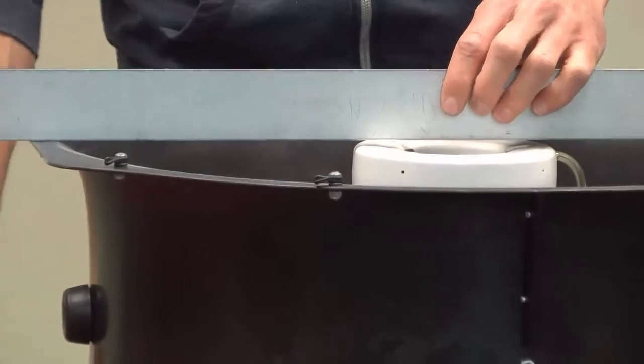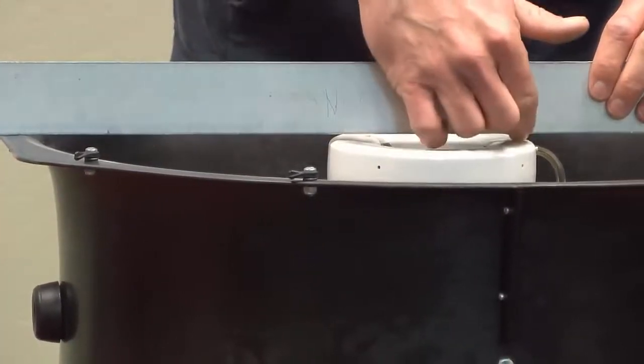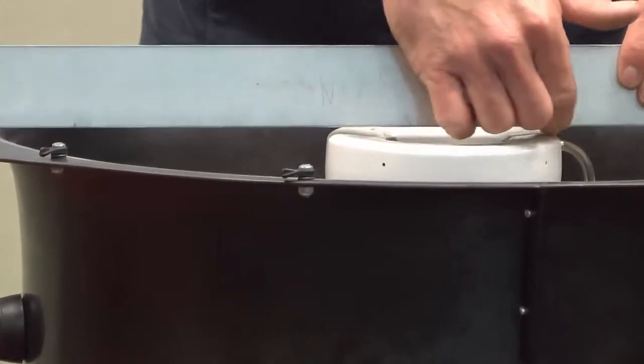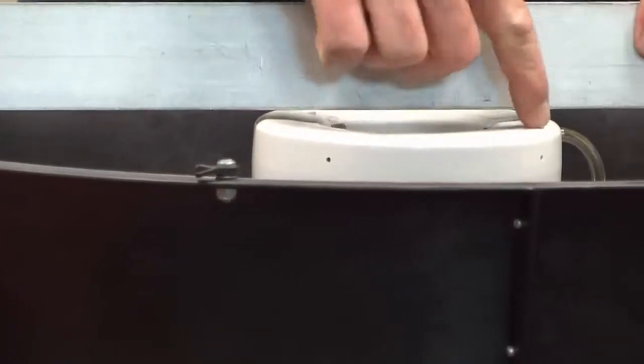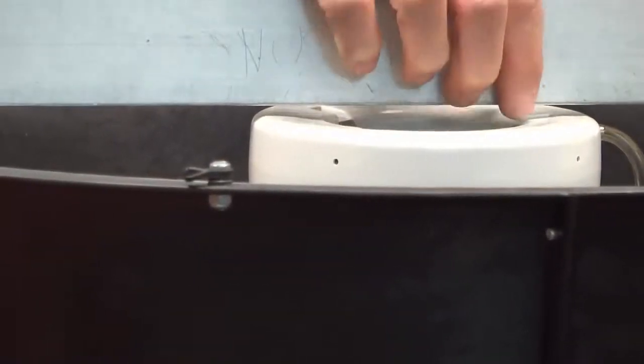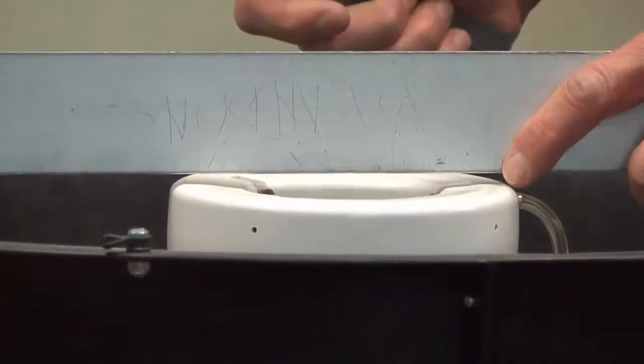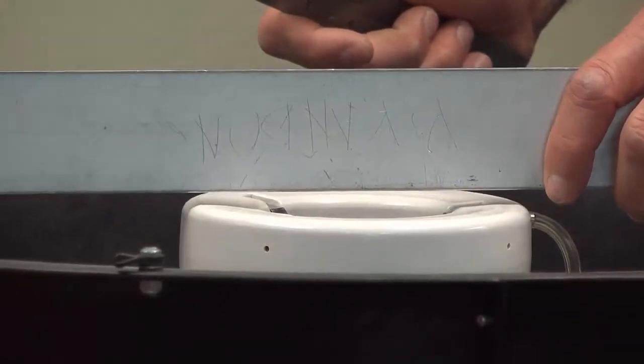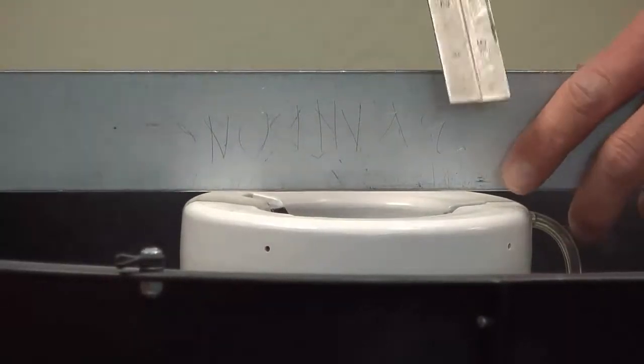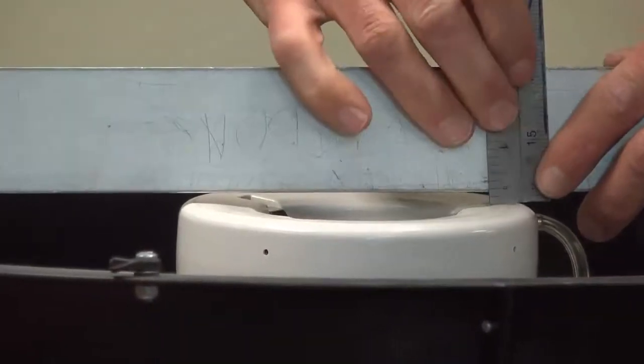Basically what we're going to be measuring is this gap between the bottom edge of our ruler and the flow sensor housing. The specification is you want to be at 1/4 inch plus or minus 1/16. So we basically want to be between 3/16 and 5/16 of an inch on here.